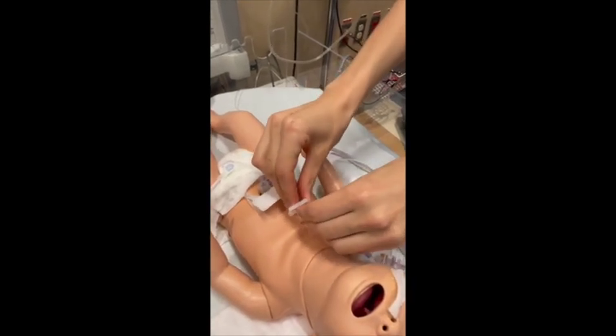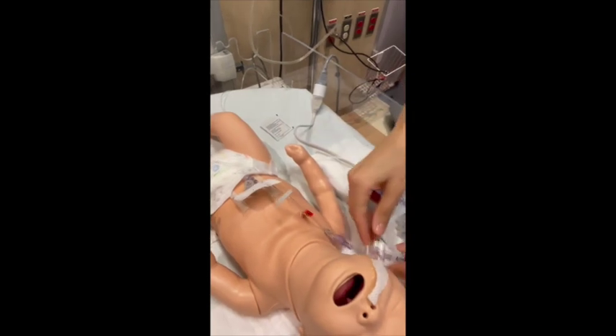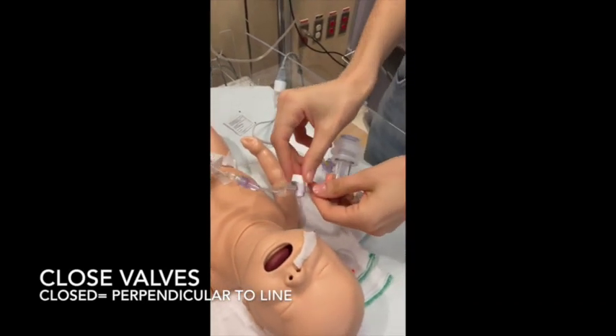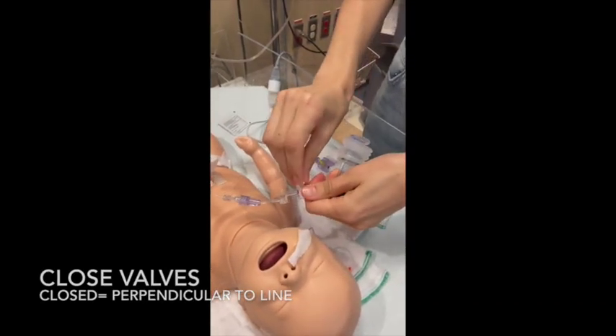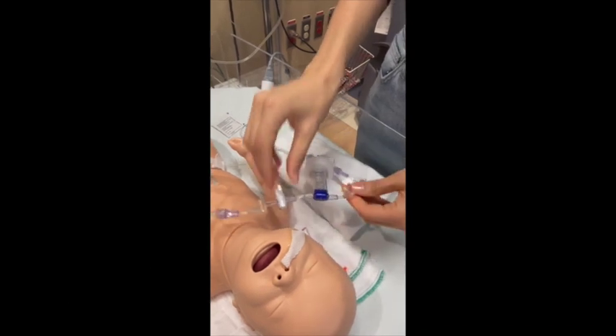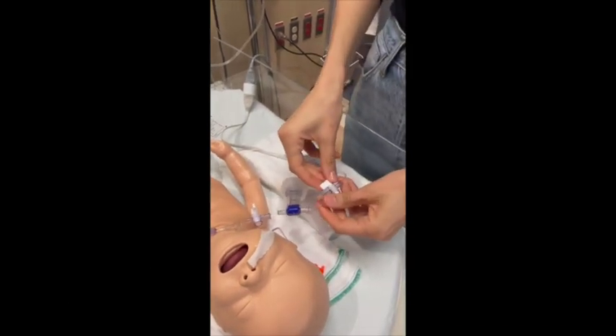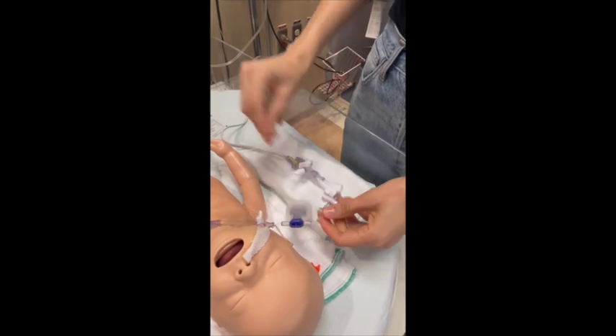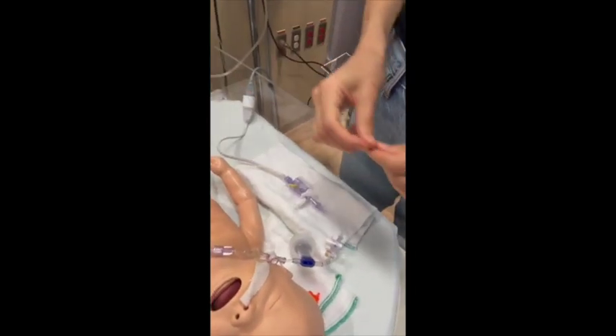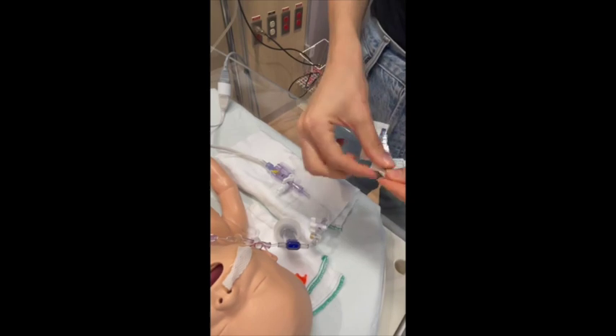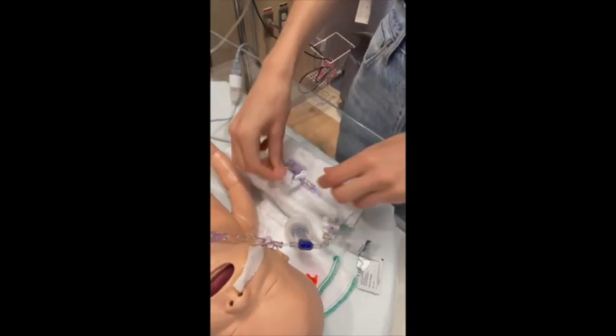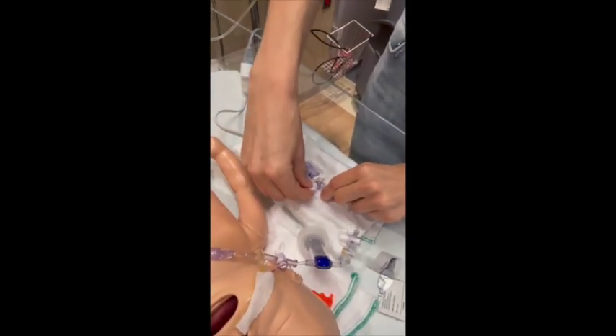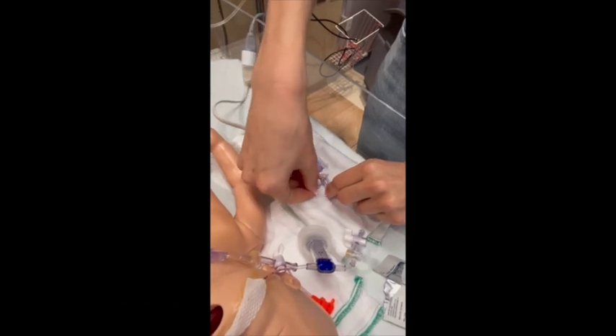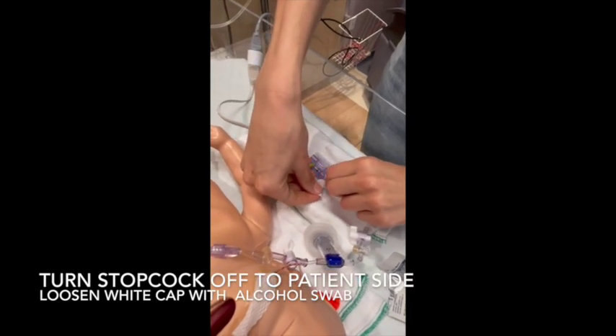Clamp the arterial line closest to the patient by either clamping the extension set or by turning the valves on the VAMP Junior off, turning the valve perpendicular to the line. It is important to ensure the line is off to the patient to prevent accidental hemorrhage. Turn the stopcock off to the patient's side.